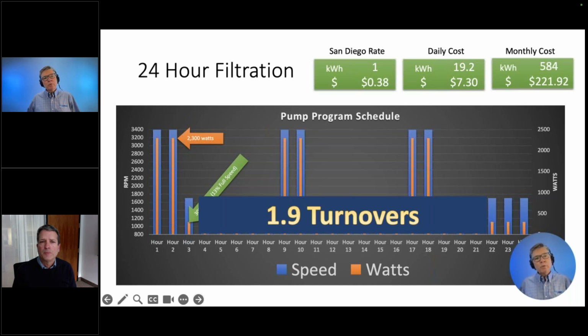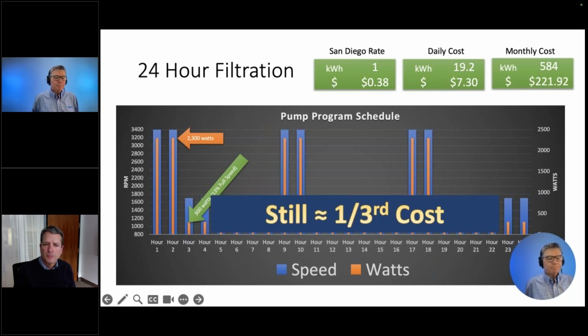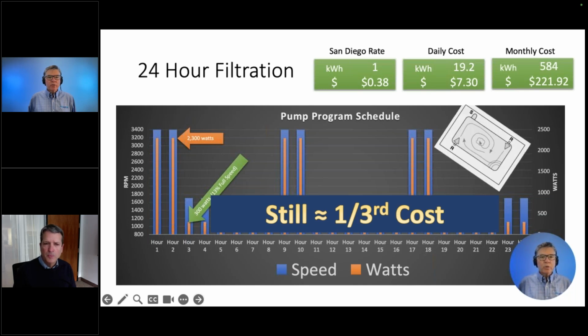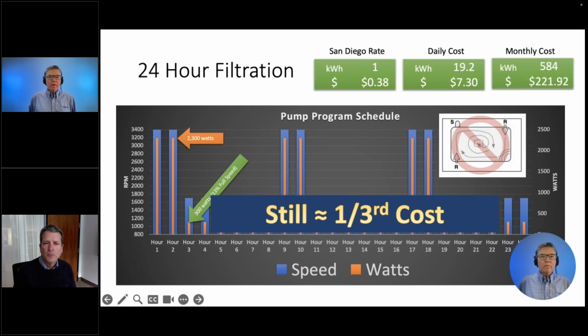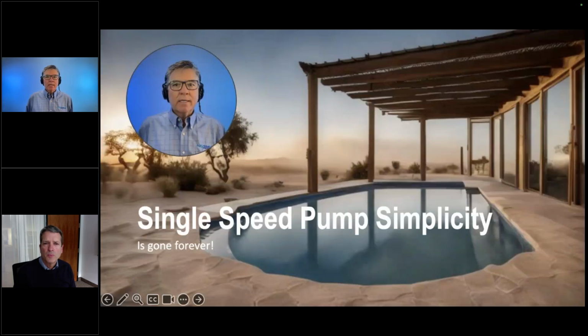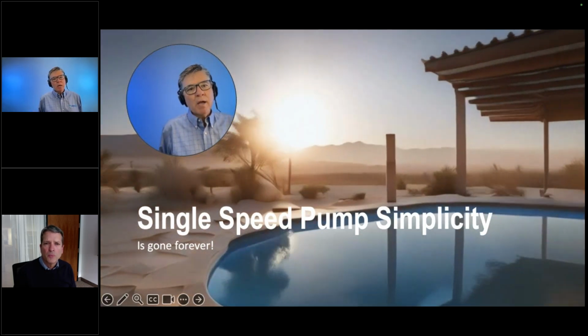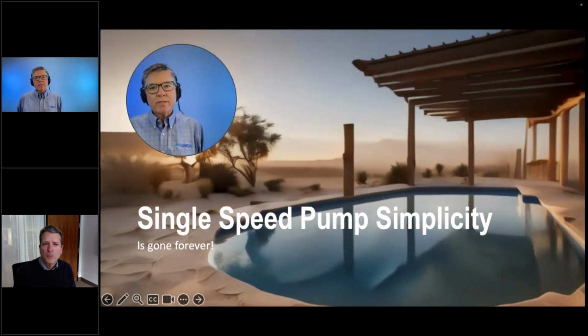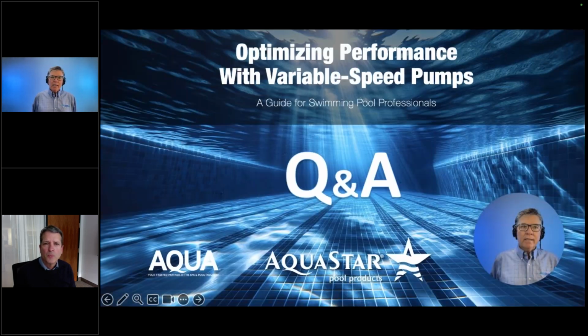The other thing is look at your local incentives on when they do and don't want you running on high speed, and adjust this accordingly. In a solar area, they want pumps on high speed during the day and off at night. So it varies by zone, but be aware of that, and think creatively for how you're doing your filtration, so that we don't have water and debris settling in the middle of the night. So the bottom line is single speed simplicity is gone forever. And hopefully this has been helpful.